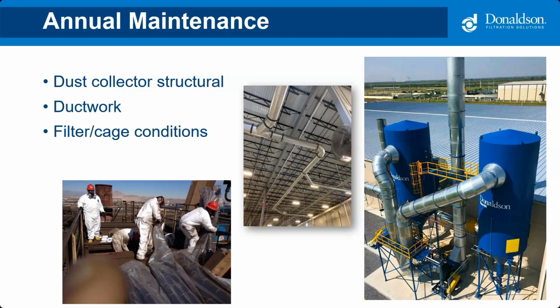Then lastly, as you're creeping up on a year, and this is more true with cartridge than with baghouse, it's probably a good time to start looking at whether it's time to do a filter change or not. You know, again, per the recommendations we said earlier. So check your filters and see if they're due for replacement.